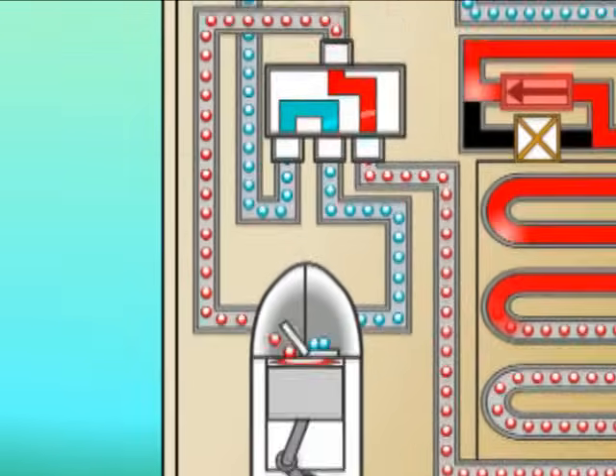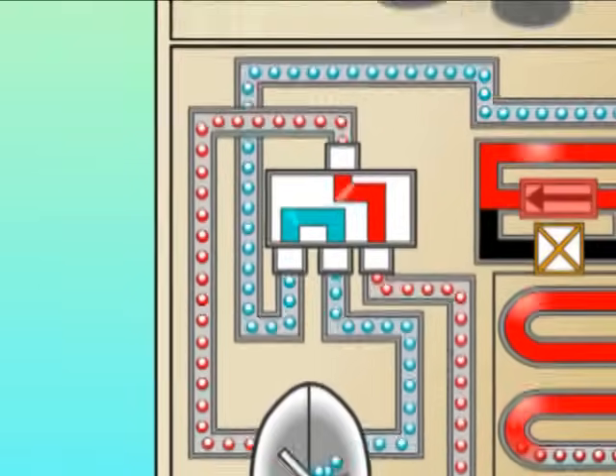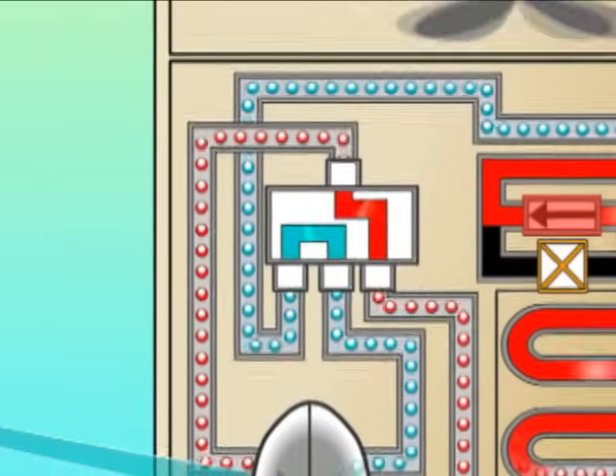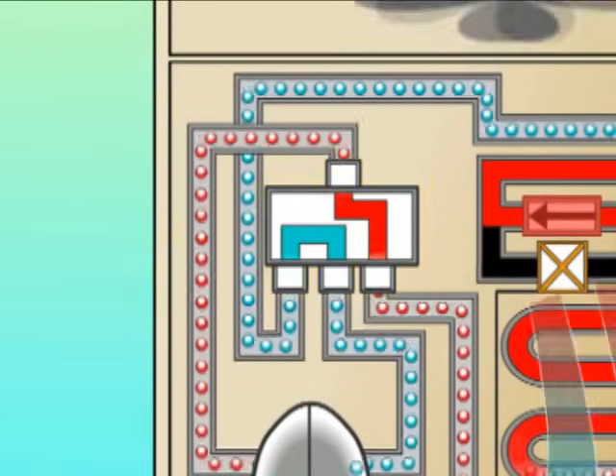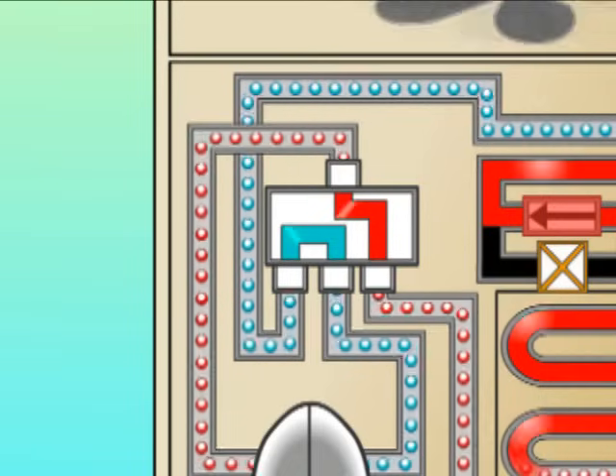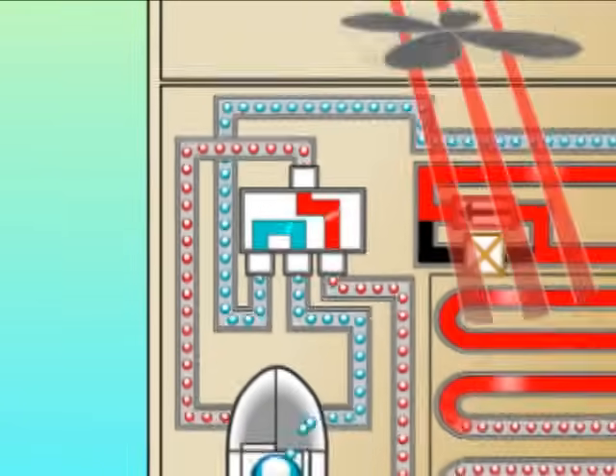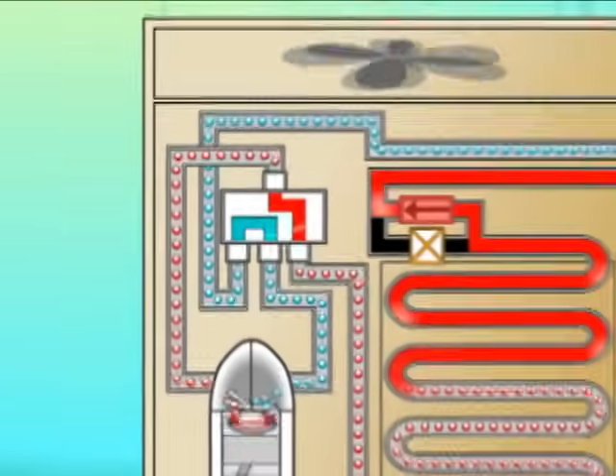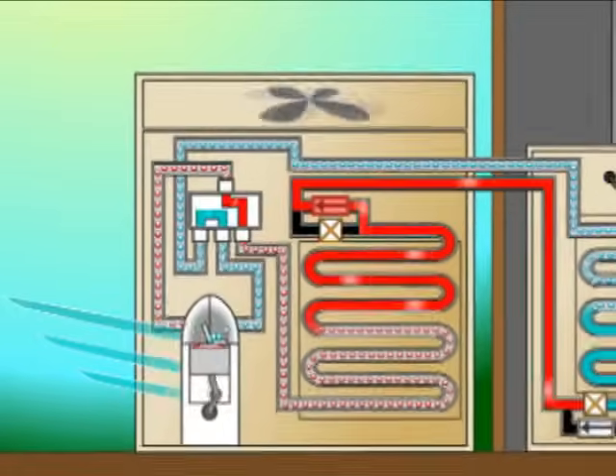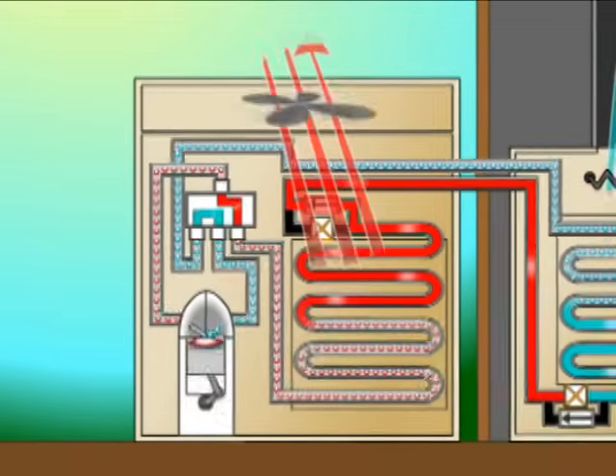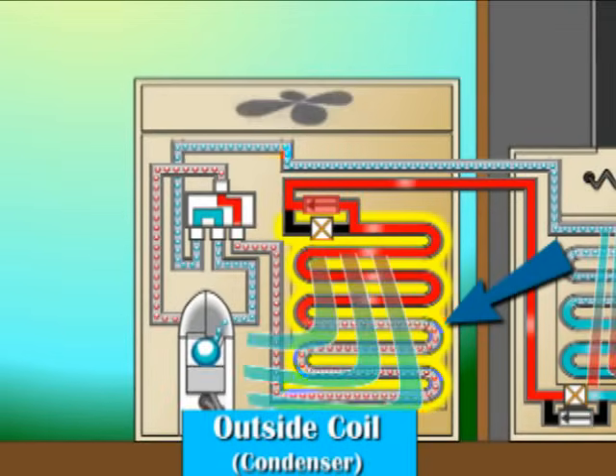This hot, high-pressure gas now travels through a routing valve known as the reversing valve to the outside coil, which functions as the condenser. In the condenser, the heat is removed from the refrigerant by the outdoor fan, causing the refrigerant to condense into a liquid.